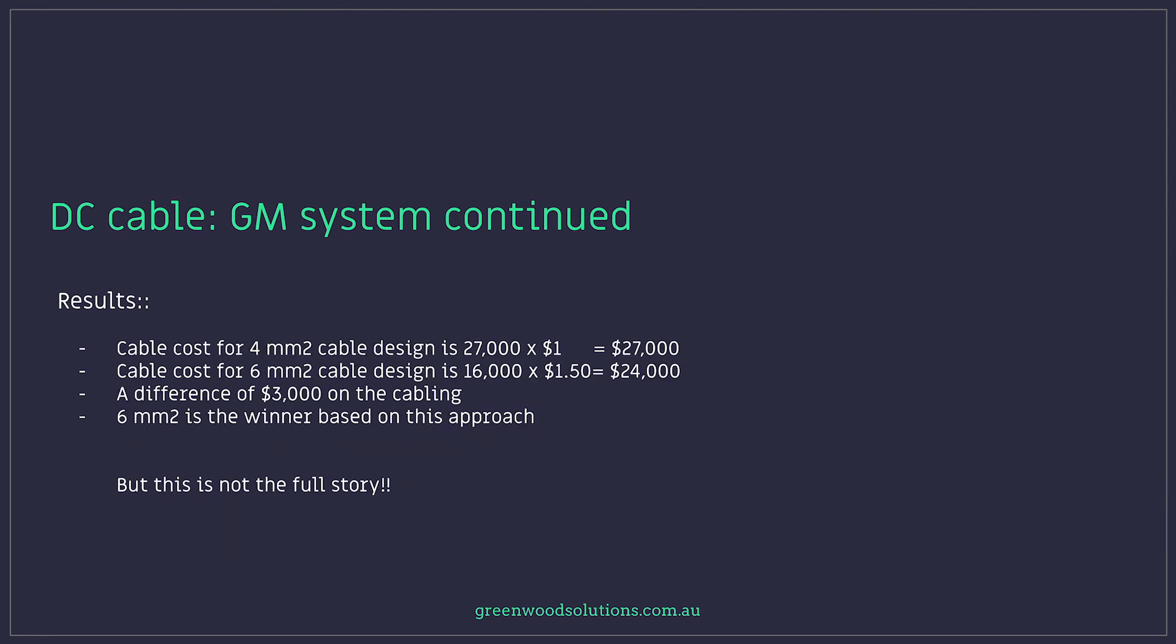The cable cost for 4mm squared is 27,000 meters times $1.00 so $27,000 for 4mm cable on that design. The cable cost for 6mm squared cable design is 16,000 meters times $1.50 because it's $1.50 per meter for 6mm and that's $24,000.